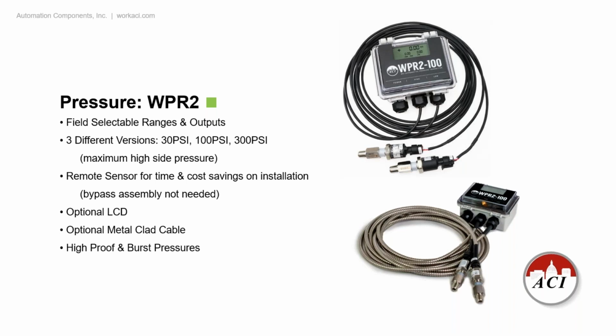You simply deplug the Packard fitting, put one sensor on the supply, one on the return, hook up the wiring, mount the unit, and it shows right away on the display the supply pressure, the return pressure, and on the top of the display, the differential pressure. So now that comes with or without a display option. 3 selectable pressure ranges. We have one unit that's a 30 PSI unit, so that's 0, 10, 20, and 30. A 100 PSI unit, so you can select 0, 25, 50, 75, and 100. And the 300 is 0, 100, 200, 300 PSI.